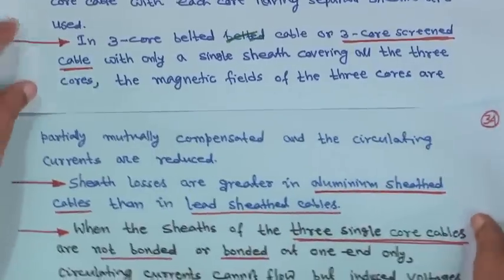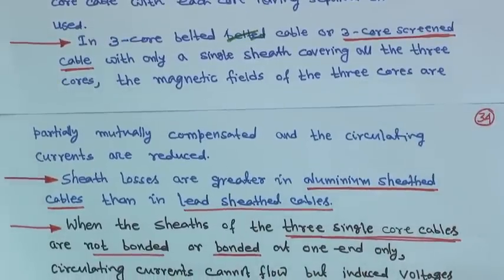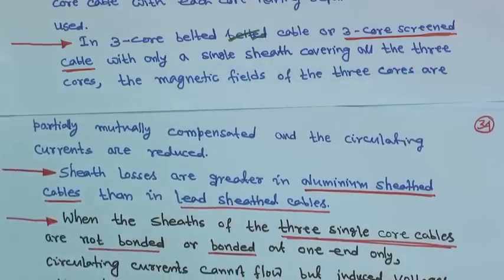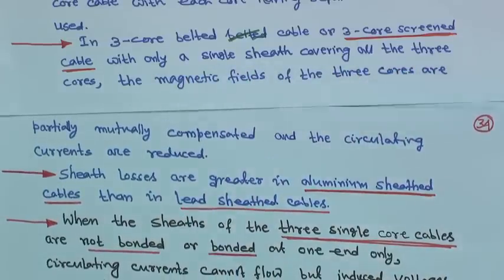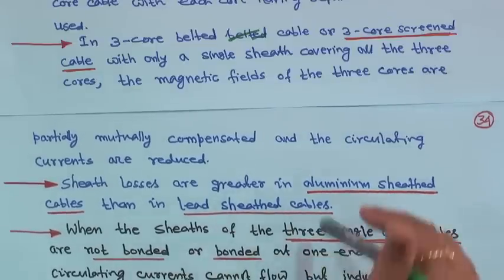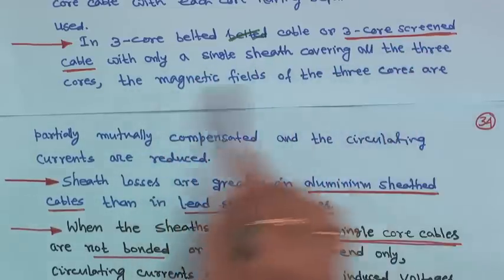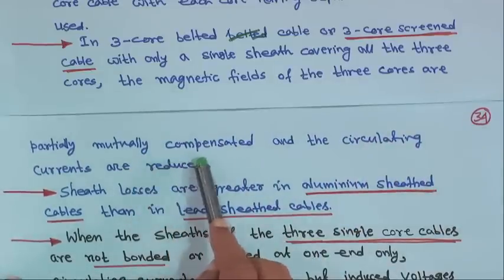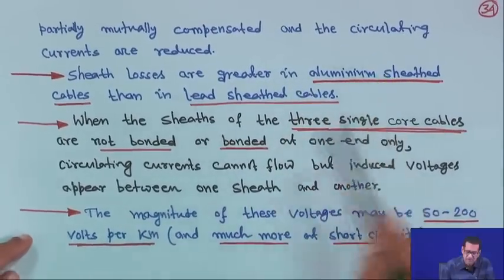In a 3-core belted cable or a 3-core screen cable with only a single sheath covering all 3 cores, the magnetic fields of the 3 cores are partially mutually compensated and the circulating currents are reduced, but sheath loss will still happen. Sheath losses are greater in aluminium sheath cables than in lead sheath cables.